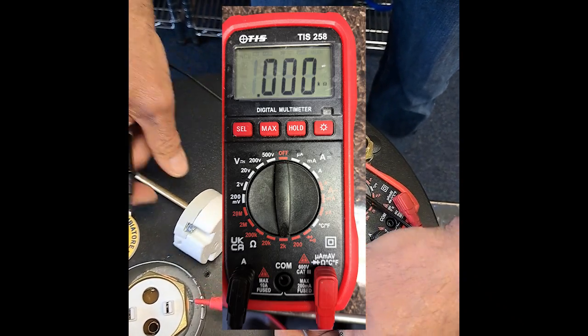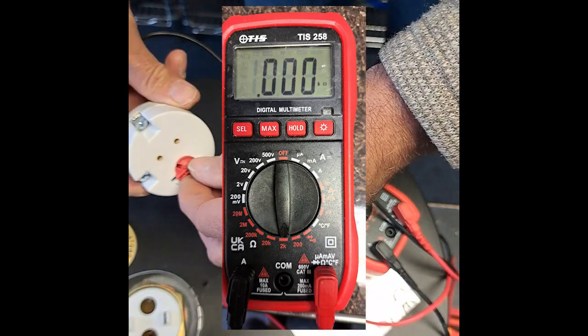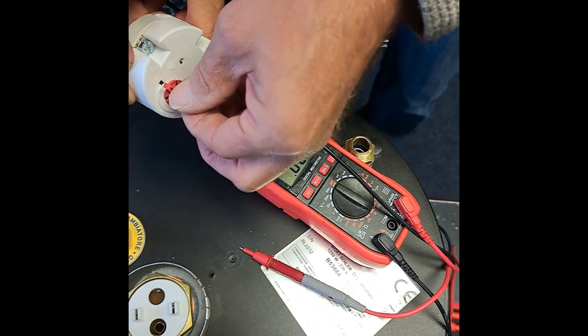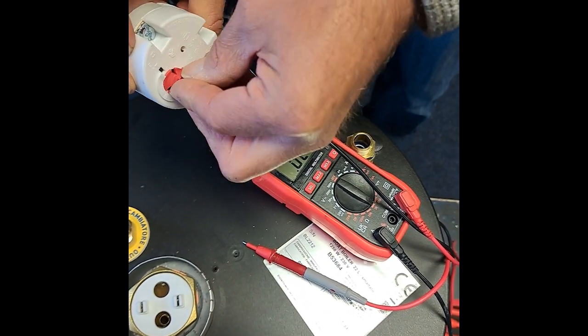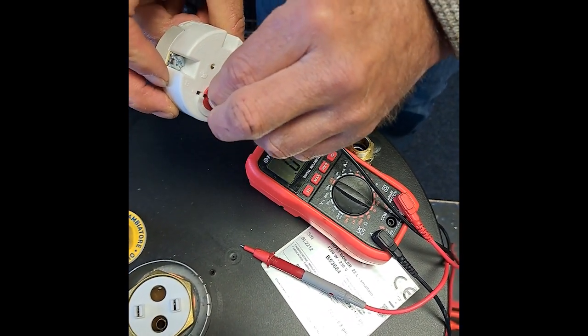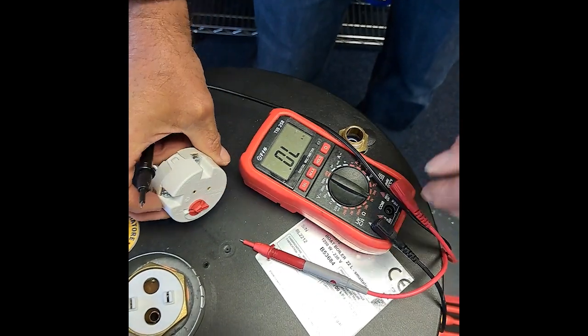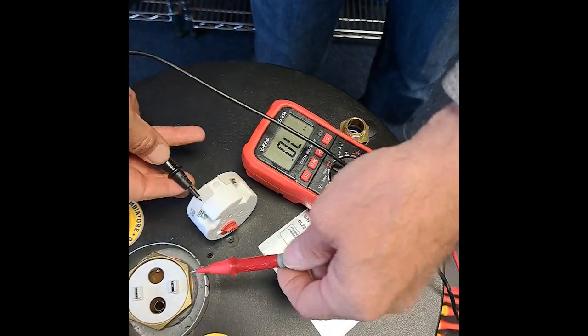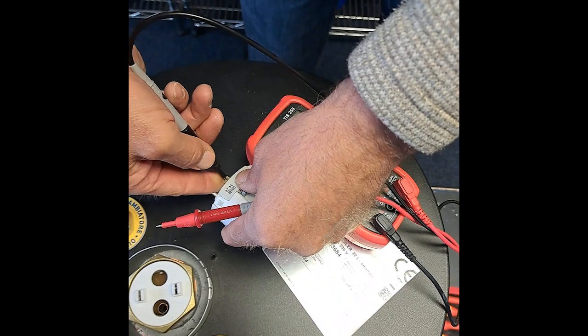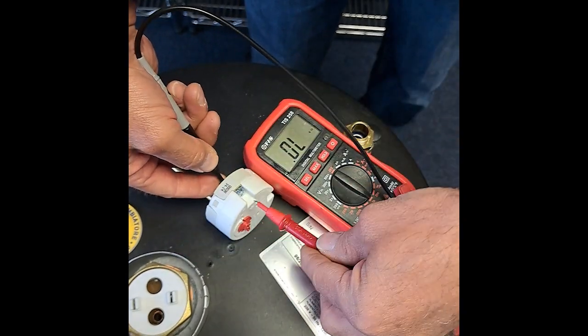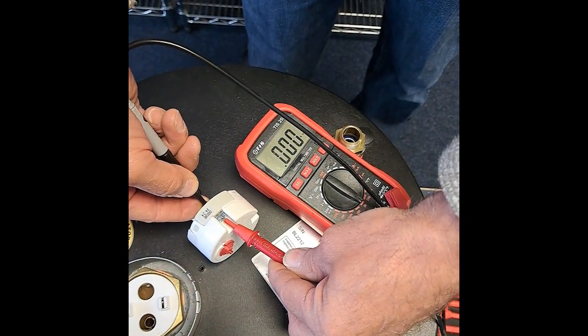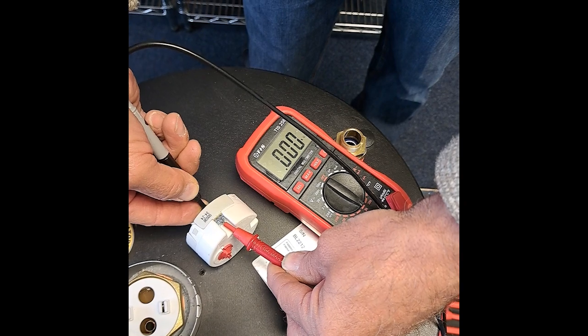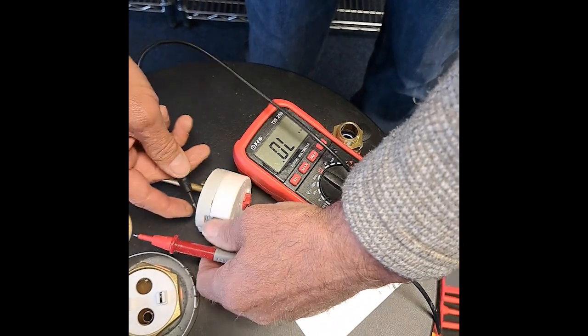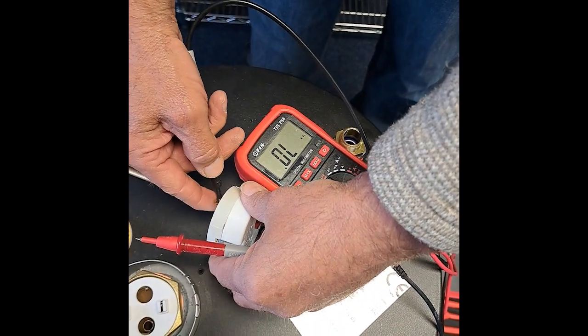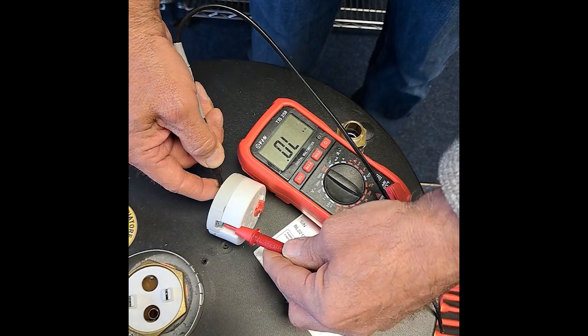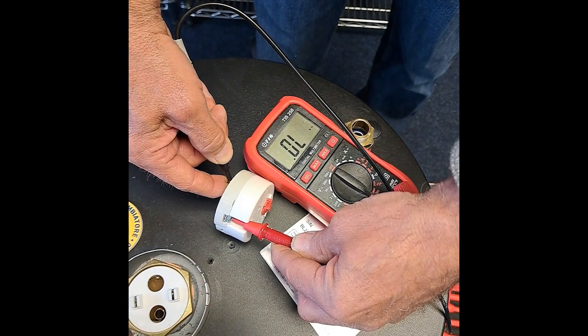Now turn the dial all the way down to 1 and you should hear a click, which is telling you that the temperature has been achieved. Put the multimeter across the neutral terminal and you can see here that it's still showing a complete circuit. Go across to the live terminals and now the circuit is open. This is telling us that the thermostat is working correctly by stopping the flow of electricity when it's reached temperature. If it's not working correctly like this, or if you have any doubts, it needs to be replaced.